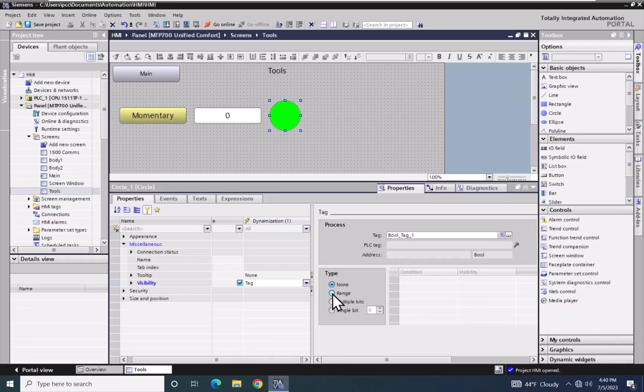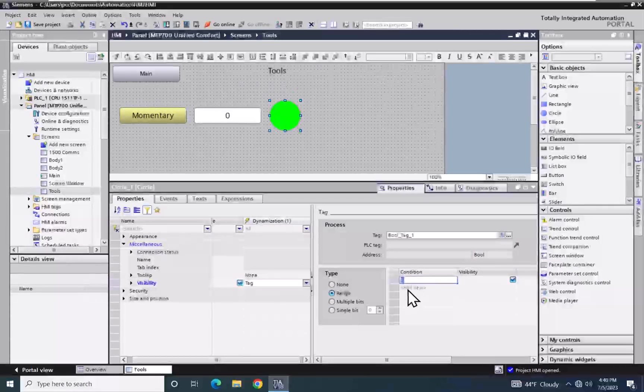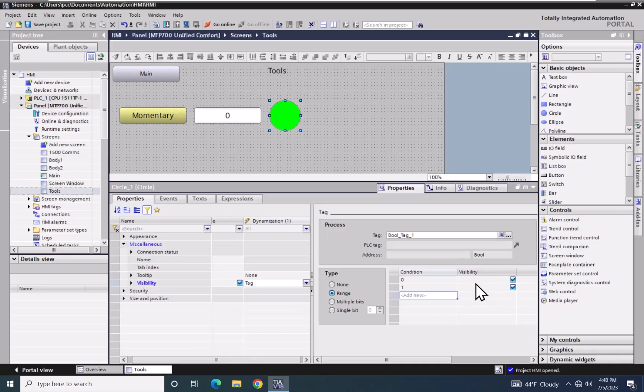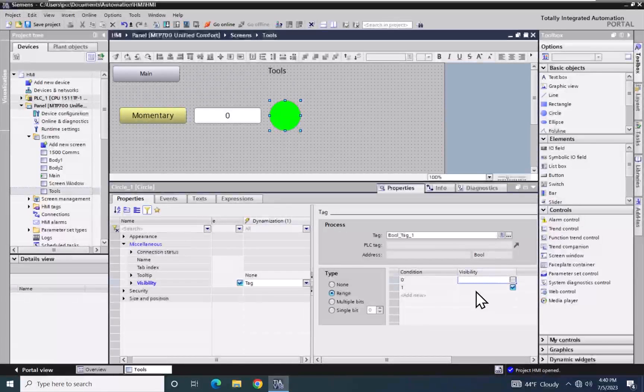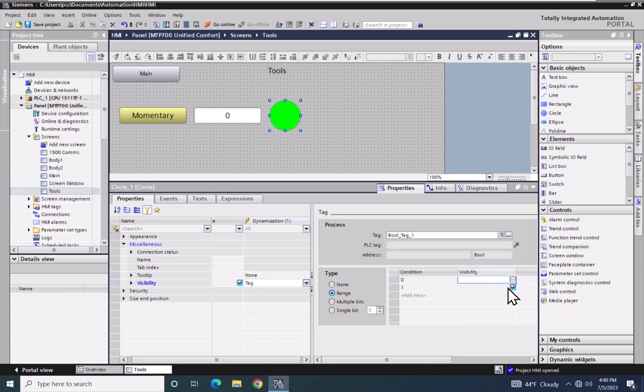I'm going to use a range animation and put in two conditions: condition zero and condition one. For condition zero, the visibility is true, and for condition one the visibility is also true by default. What I want to do is change condition zero — so when my tag is equal to zero, the object will not be visible. When my bool tag underscore one is equal to one, the object will be visible during runtime.